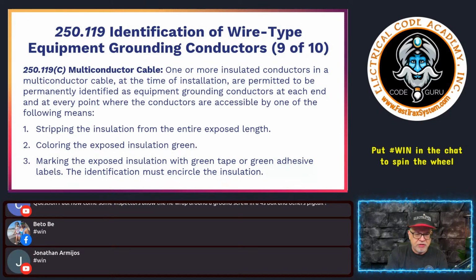All right, it's not necessarily required to be a green screw, but it is required to be green as a main bonding jumper, a green finish. It is required to be green if it is on a device like a switch or a receptacle, that type of thing. In a box, not necessarily required to be green, although usually those screws are sized properly for an already tapped location where the equipment ground would go.